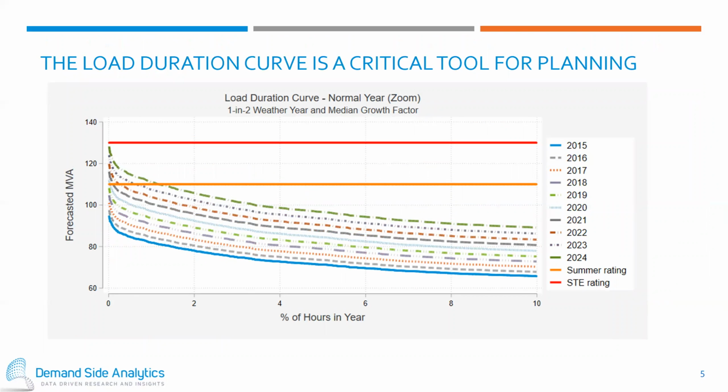curve. And for those who are not quite as familiar with the load duration curve, what a load duration curve does, it stacks data, historical data, for the highest peak hour first, the second, the third, and so forth. And you can do this when you're looking at historical data, or you can do it looking at 8760 hourly data, annual hourly data for forecasted years.